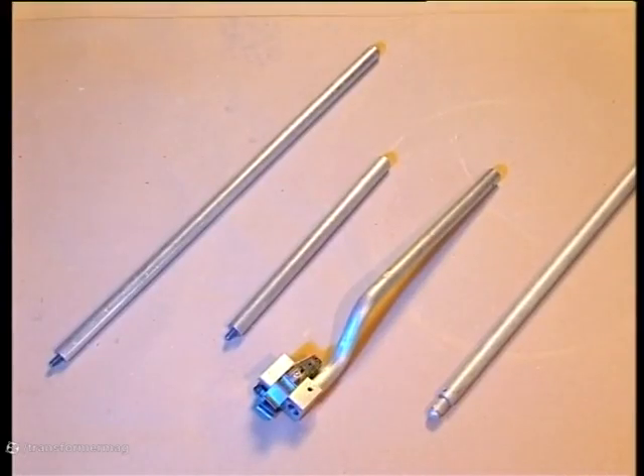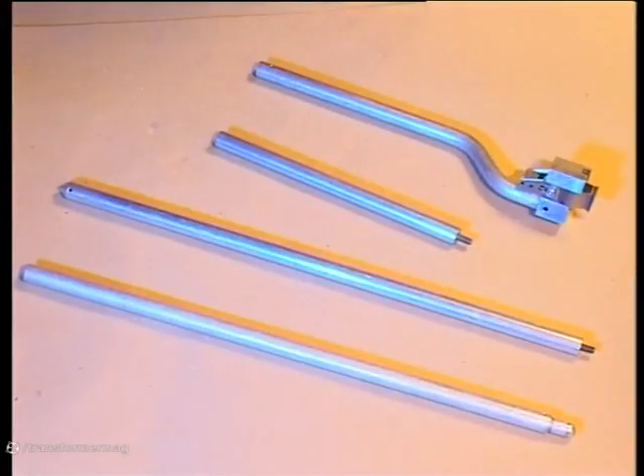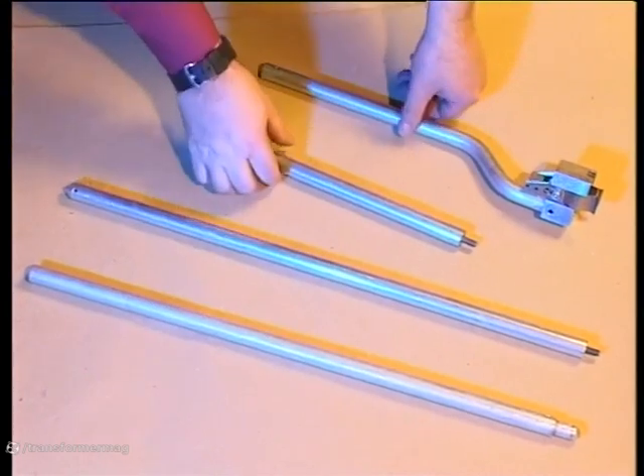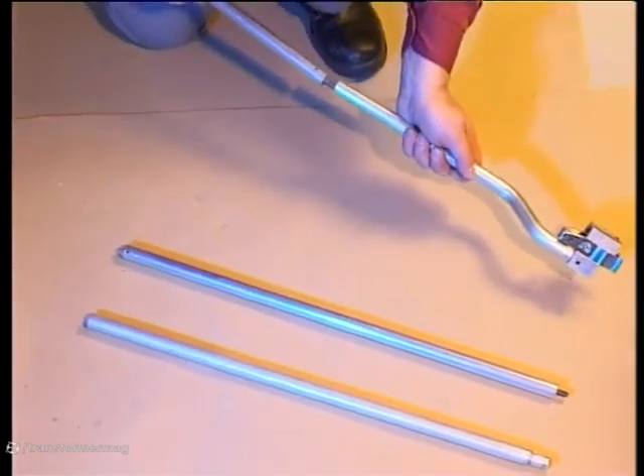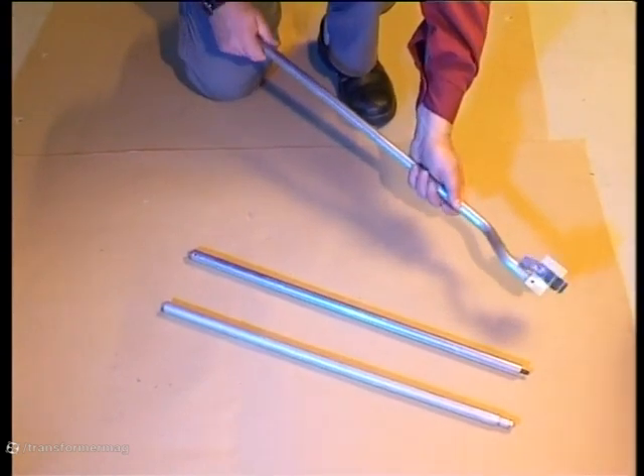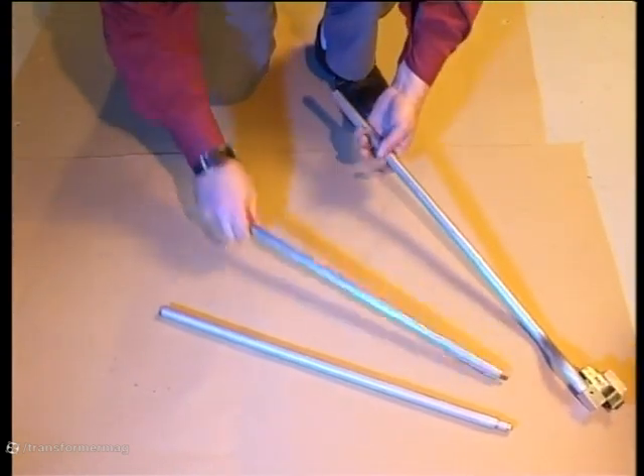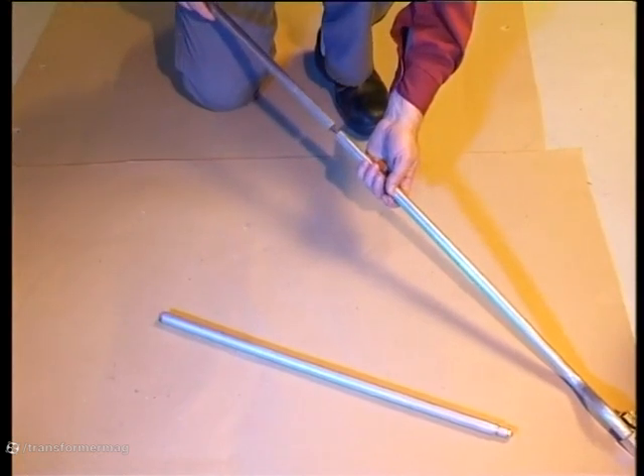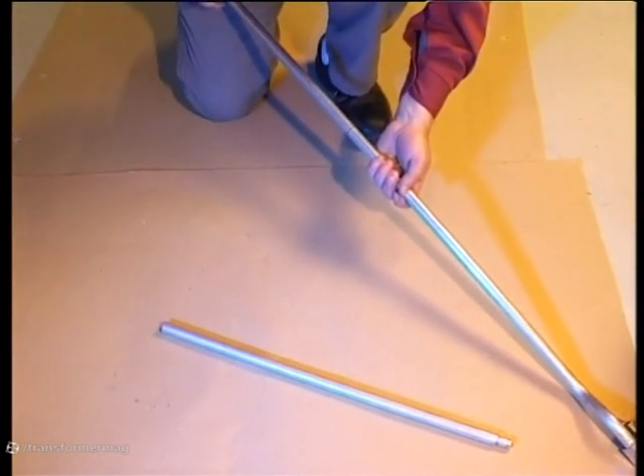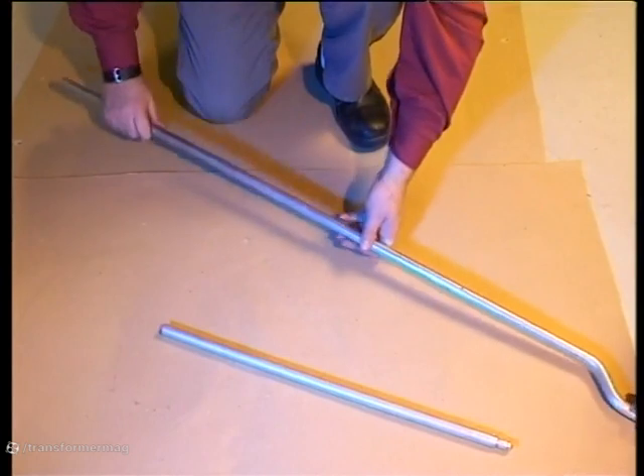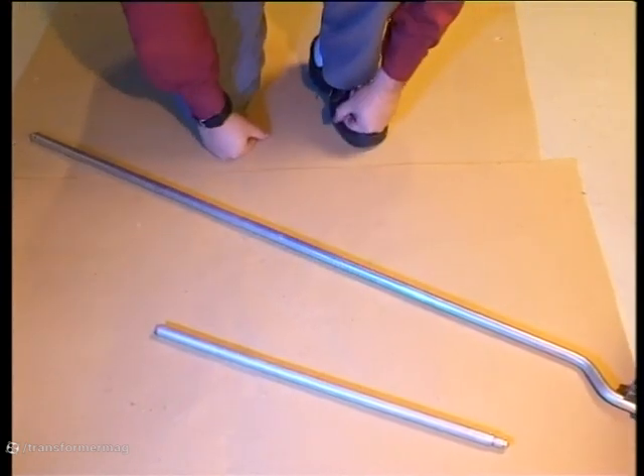This is the contact tool which is used when installing and removing fixed contacts and as a guide when reinstalling the tap changer insert. This is how to assemble it to use it as a contact tool. The same tool is used as a guide for the tap changer insert.